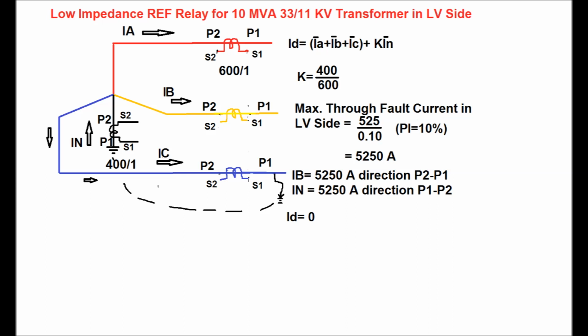Since ID is given by the vector sum of all three phase currents plus K into IN, this sum of the phase currents plus factor K into IN comes as 0, since the blue phase current flows from the direction P2 to P1, but in the case of the neutral CT the direction is opposite to that of the blue phase current, so ID is 0.